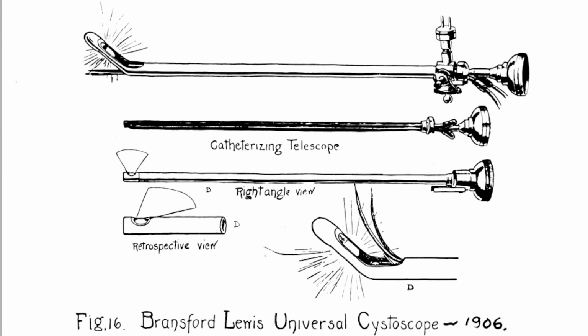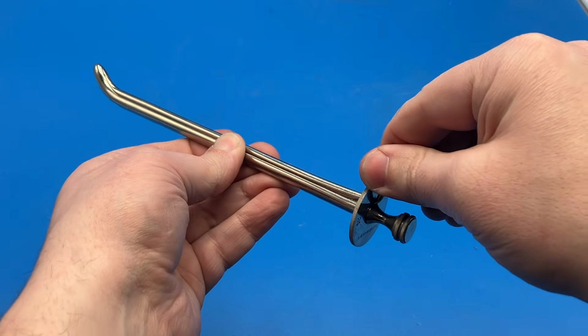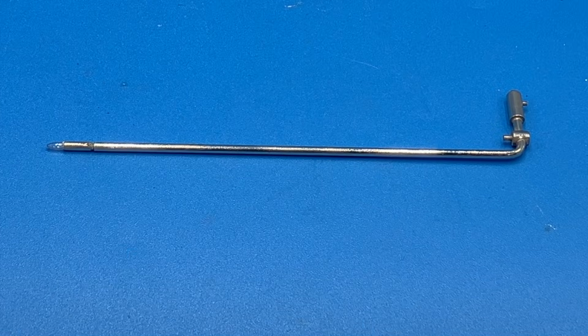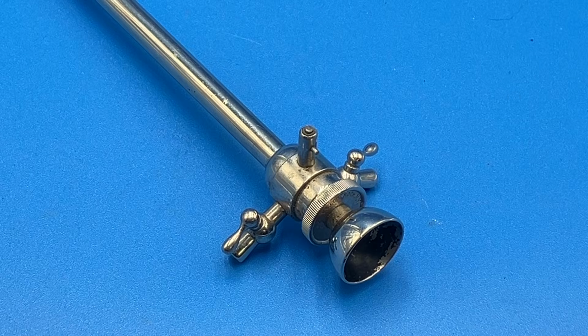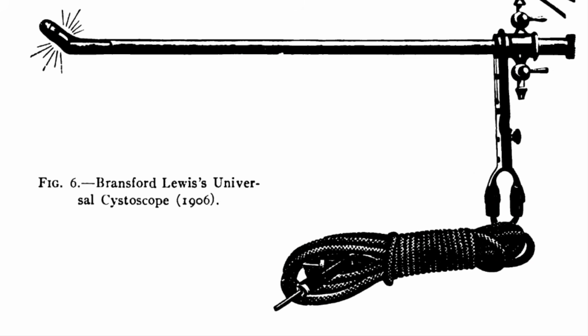Most earlier cystoscopes had the bulb mounted at the tip, casting most of its light uselessly away from the observation lens. By contrast, in this instrument, the lamp is mounted to a separate probe or light carrier which can be slid down the barrel. In both cases, the bulb is connected on one side to this inner core of the bayonet connector via an insulated wire, the circuit return being through the instrument itself and the outside of the terminal.